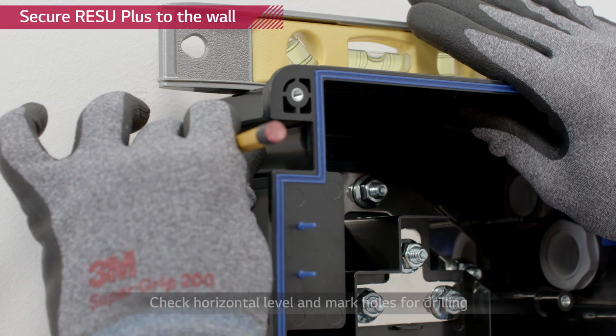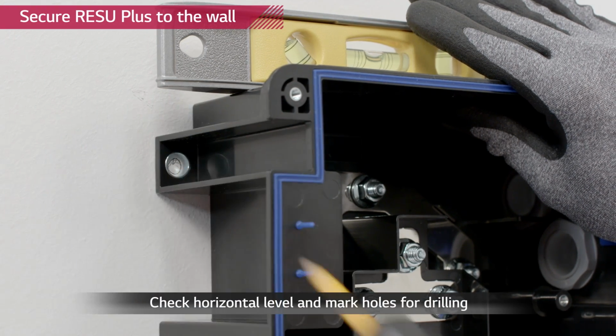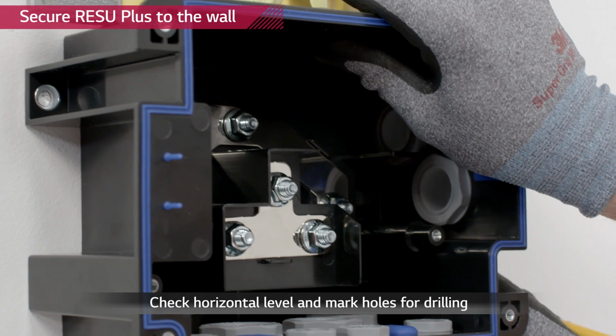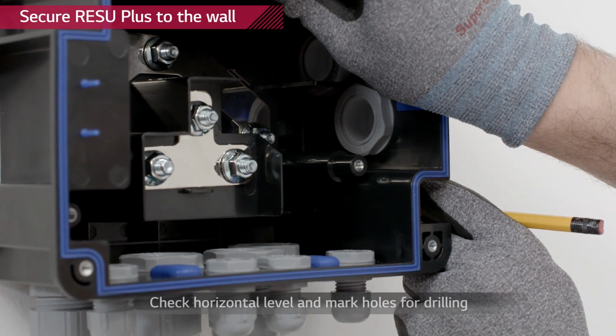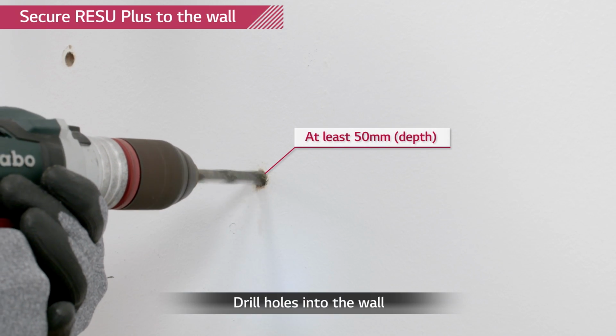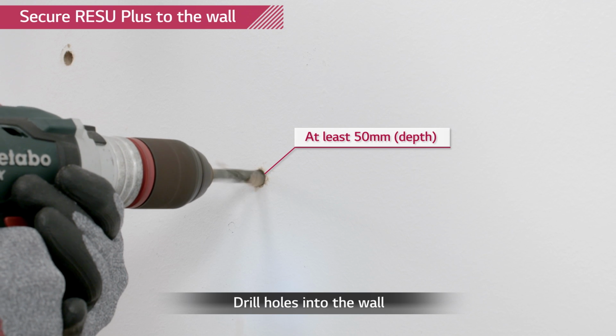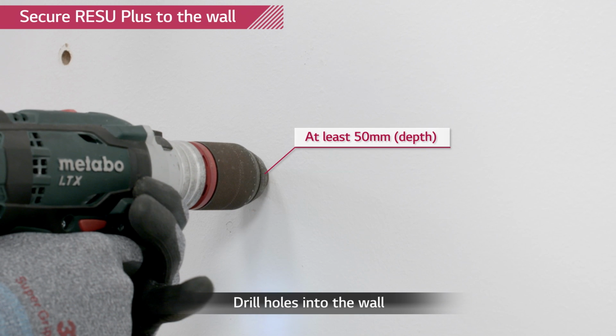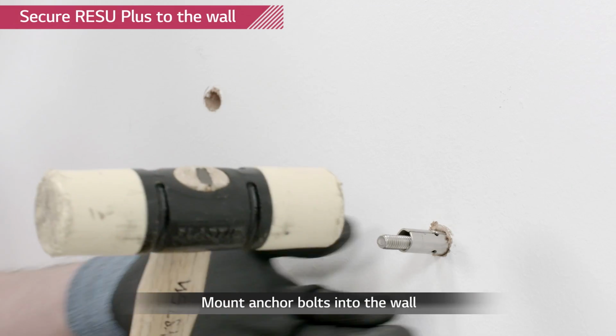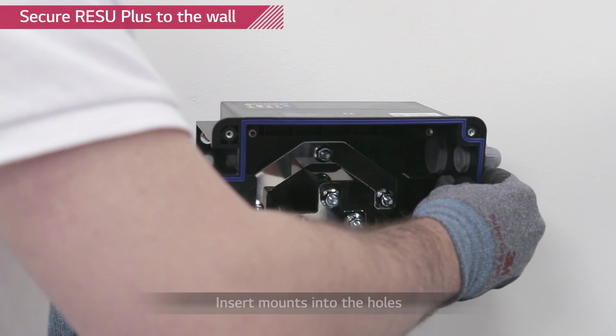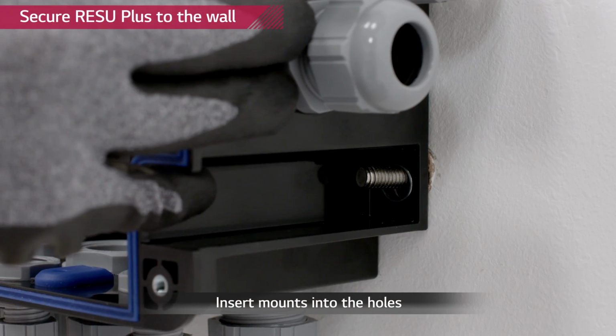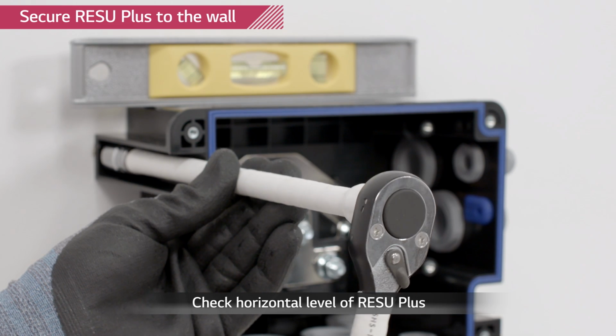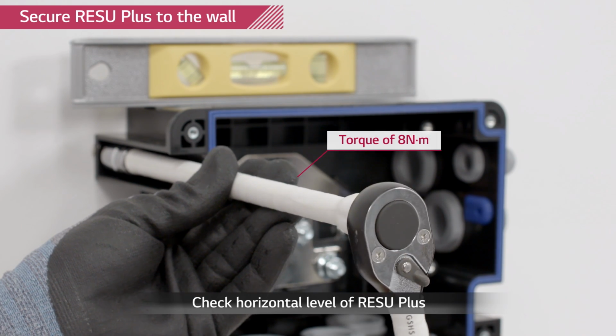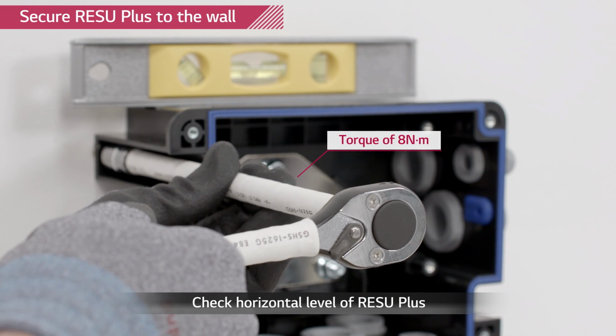Determine mounting position by using the mounting holes which are placed on the left top and right bottom side of the device. Drill holes into the wall for M8 screw anchors. The drilling depth should be at least 50 millimeters. Drive the screw anchors through the holes of the device into the drilled wall. Tighten the screws with a torque of 8 Newton meters.